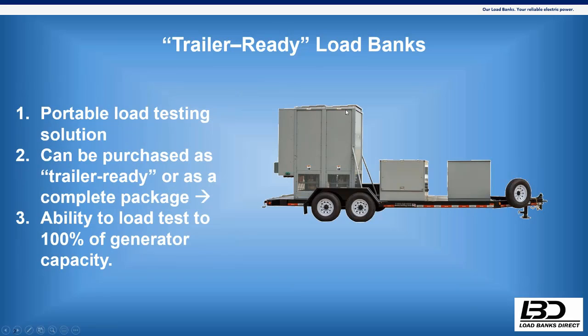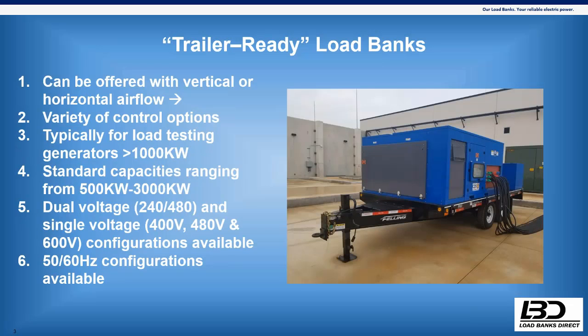The overall height of this unit, mounted on the trailer, is close to 10 feet. So you're never going to get something like that into a low ceiling space. You can get the load bank in there, but you don't have enough area to exhaust vertically without causing issues—similar to the issue you experience with the horizontal units, just out the end instead of vertically toward the ceiling.